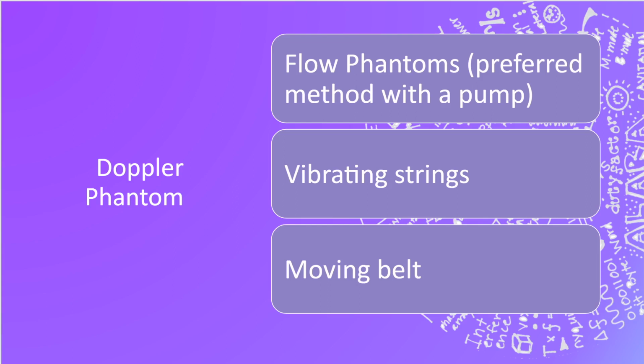They basically have a tube within them and a pump. The pump will move fluid through the tube at a set rate, so you always know it's moving at 75 centimeters per second or something like that. And then you can test, are you getting the right color flow, the right color direction, good registration of the color, is all of that working? And so the flow phantom is the preferred method to test our Doppler instrumentation.